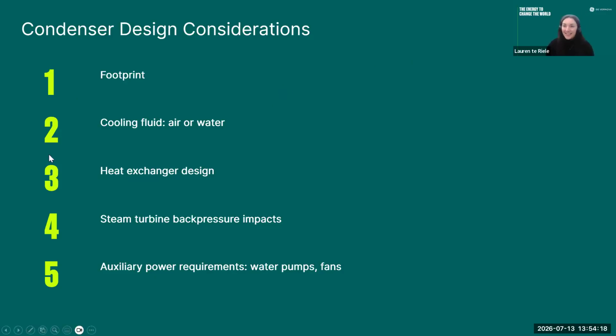Second, as implied, you have to choose your cooling fluid - is there any limitation on the availability of fans or of sourcing water to create the cooling fluid you need? Third is the heat exchanger design you want to consider. You just went through heat exchanger design, so hopefully you have some ideas in your head - parallel flow, counterflow, water box as the example I gave before. There are a lot of different opportunities for how you design your heat exchanger once you've decided your cooling fluid.